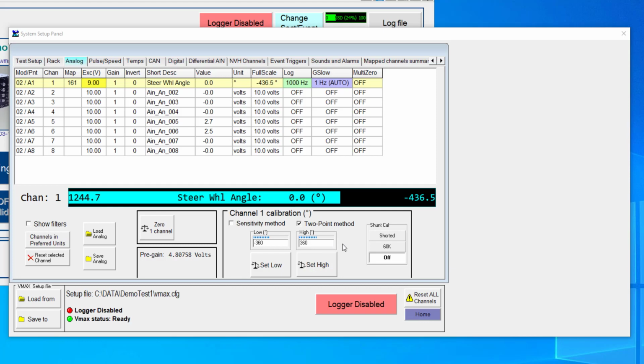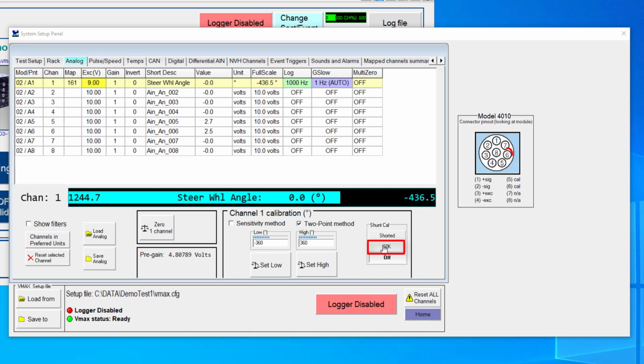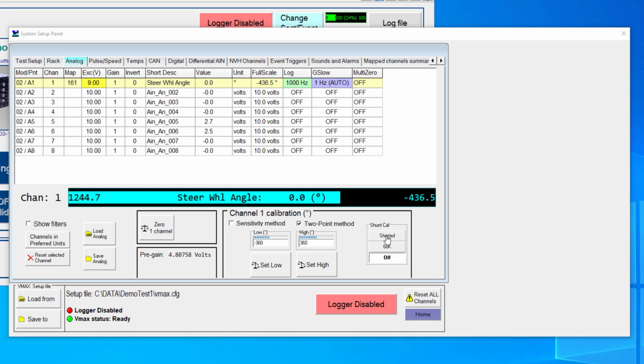Now we do also have the ability to apply a 60K shunt resistor across 2 pins on the LEMO connector, and we can also do a cal shorted, which, in the case where you have a shunt resistor that is built into your cable, you can actually apply that electrical shunt to the sensor. We use this quite often on sensors like load cells and pressure transducers, where we may have a sensitivity method that we enter in to do our calibration, but then we use a shunt resistor to verify that with a 59K or 60K load from a resistor, the sensor is outputting in the way that we would expect it to. So that is a nice feature that we have built in.